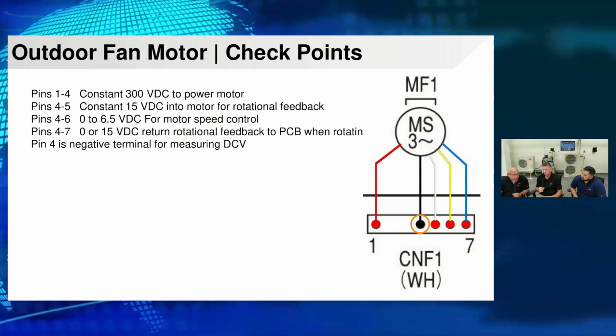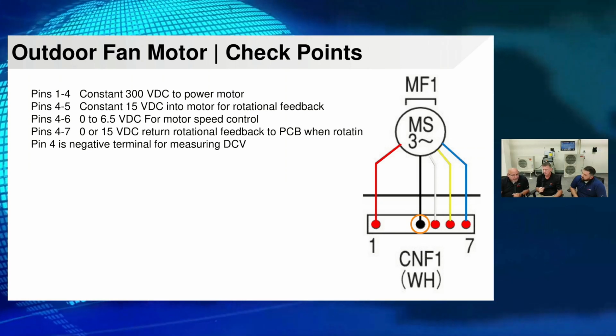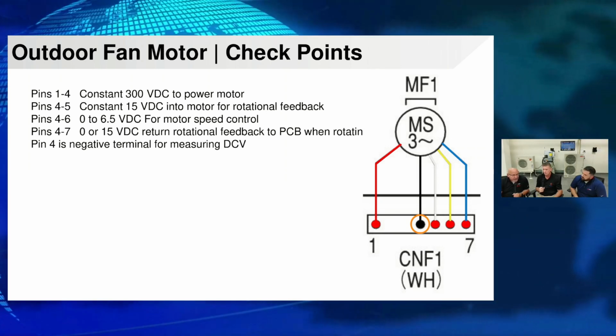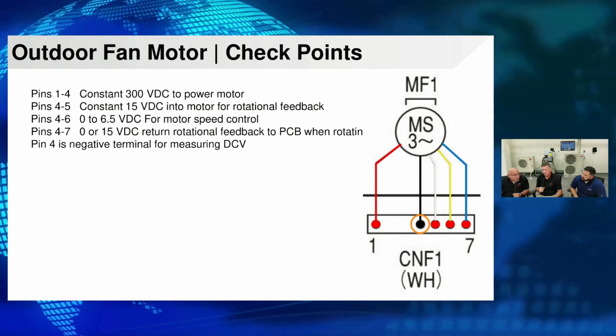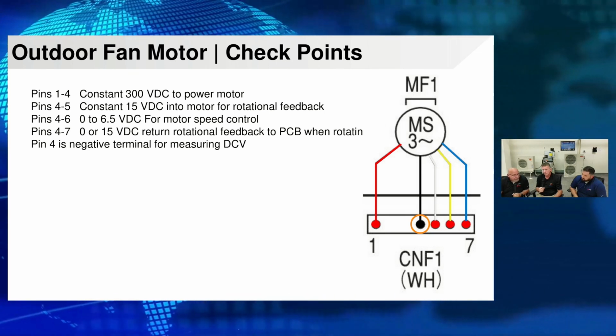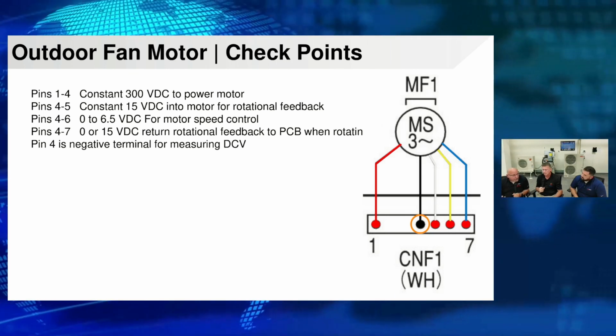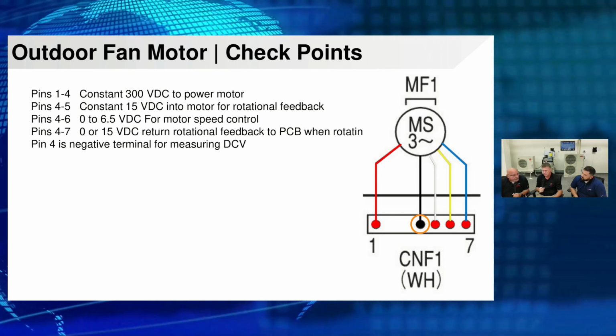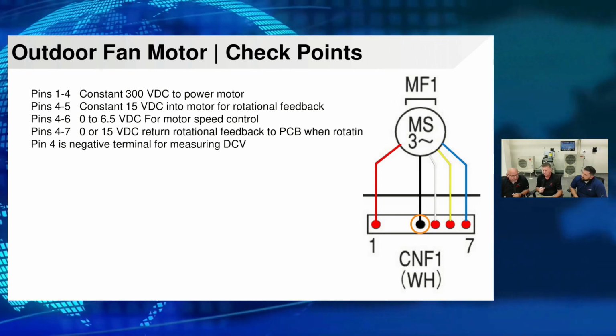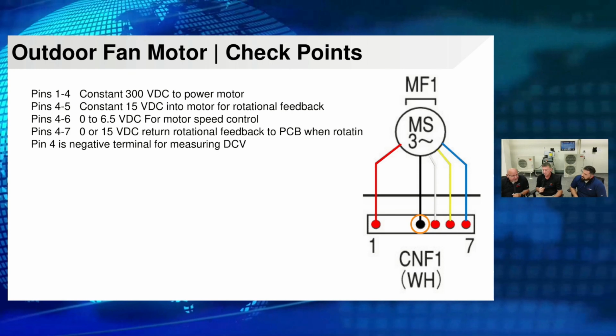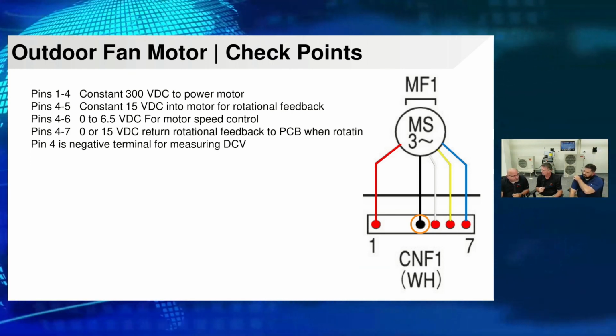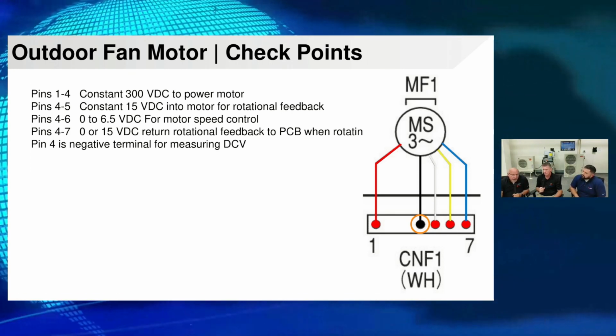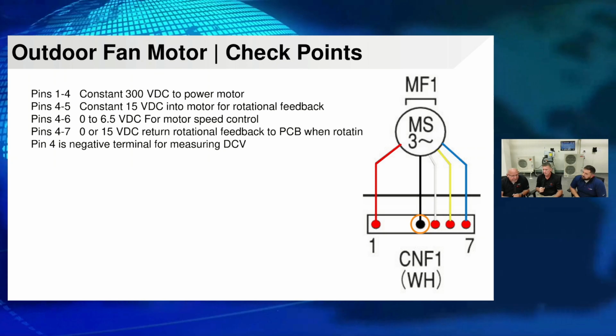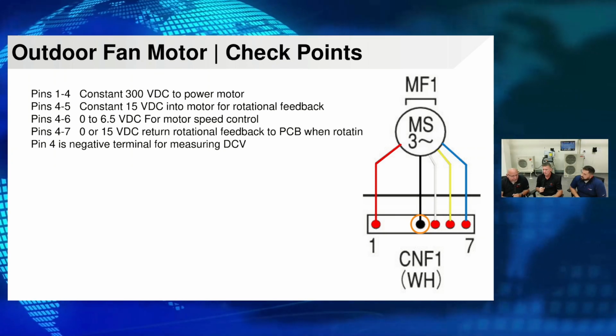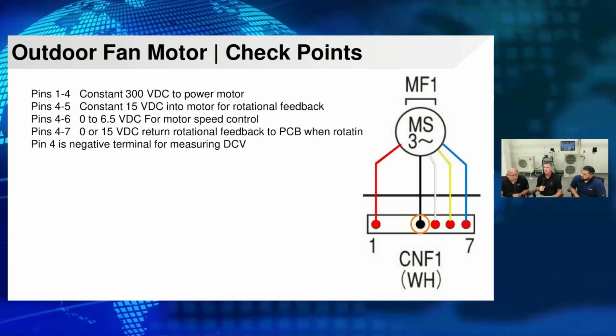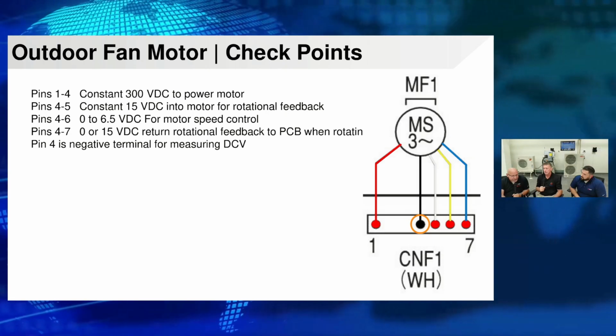That's where your 300 volts comes out of the circuit board into the motor. In this scenario, the inverter board is inside the motor, so it's going to take those 300 volts DC and invert them into a simulated, balanced 3-phase signal going into the windings internally. Pins 4 and 5 is also an output from the circuit board, which is 15 volts DC. That's your feedback again.